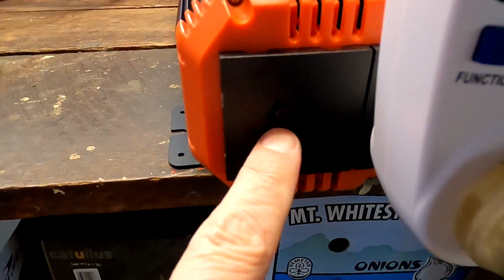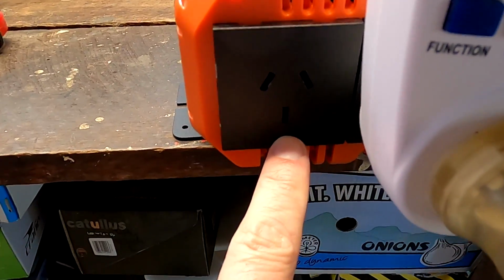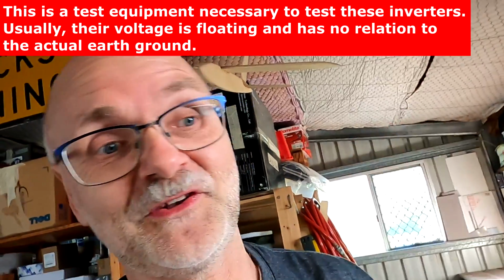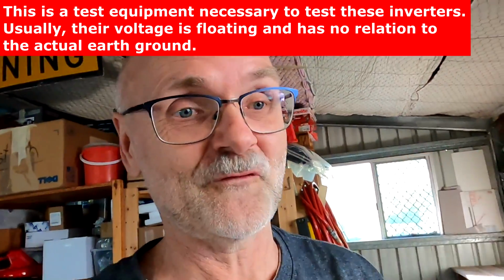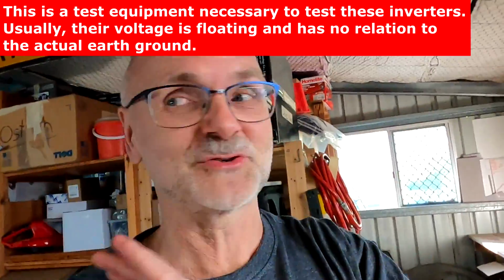Not sure if the Tesla adapter actually works with the inverter right away, or if we need to do the modification with the MEN link. Let's plug it in and see what happens. Red. Okay, let's take our adapter cable in between, and we've got a green light. This MEN adapter only links the ground cable to one of the two actives, making one the active and one the neutral, and connecting the neutral and earth together. This adapter is only for testing purposes here when I test these off-grid inverters. It cannot be used in any other way, and you should not do this at home.